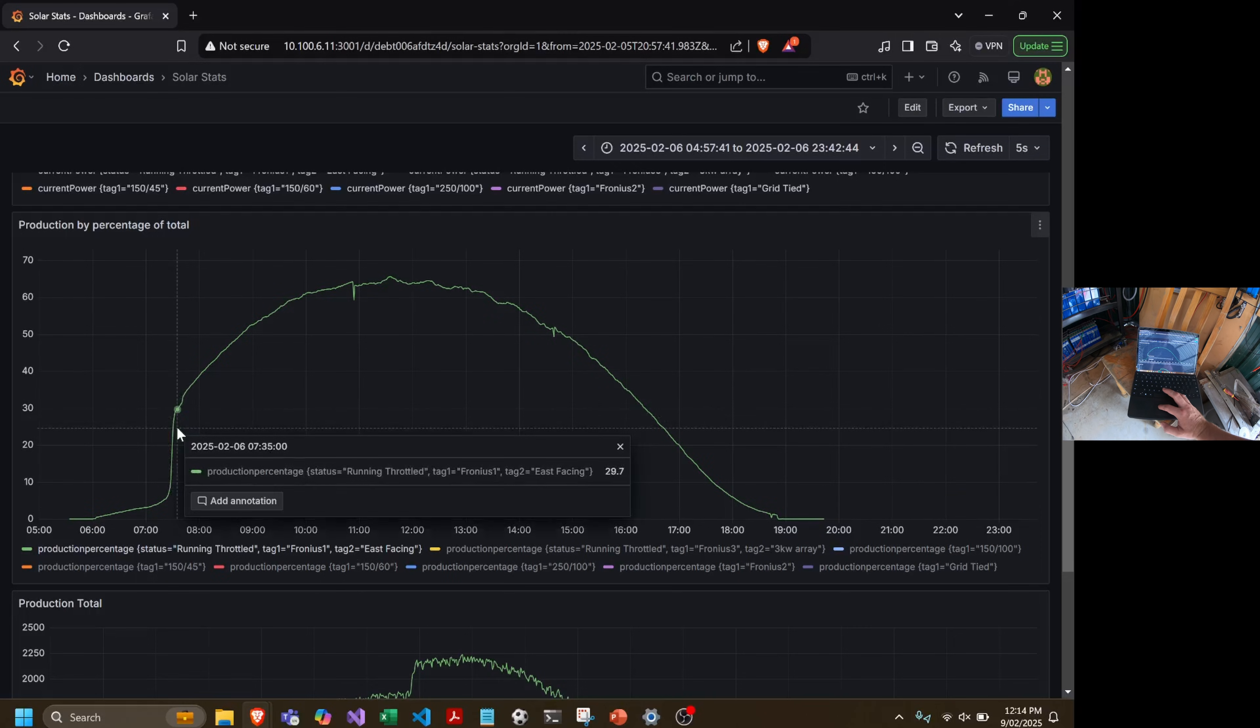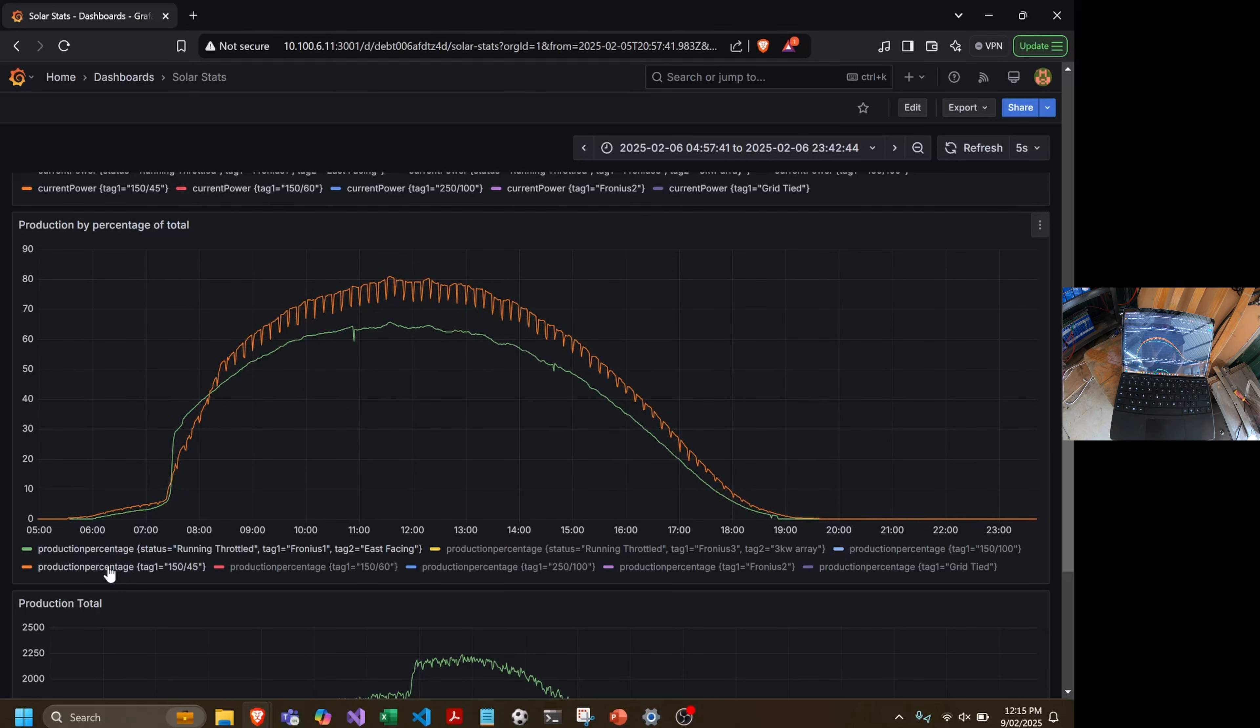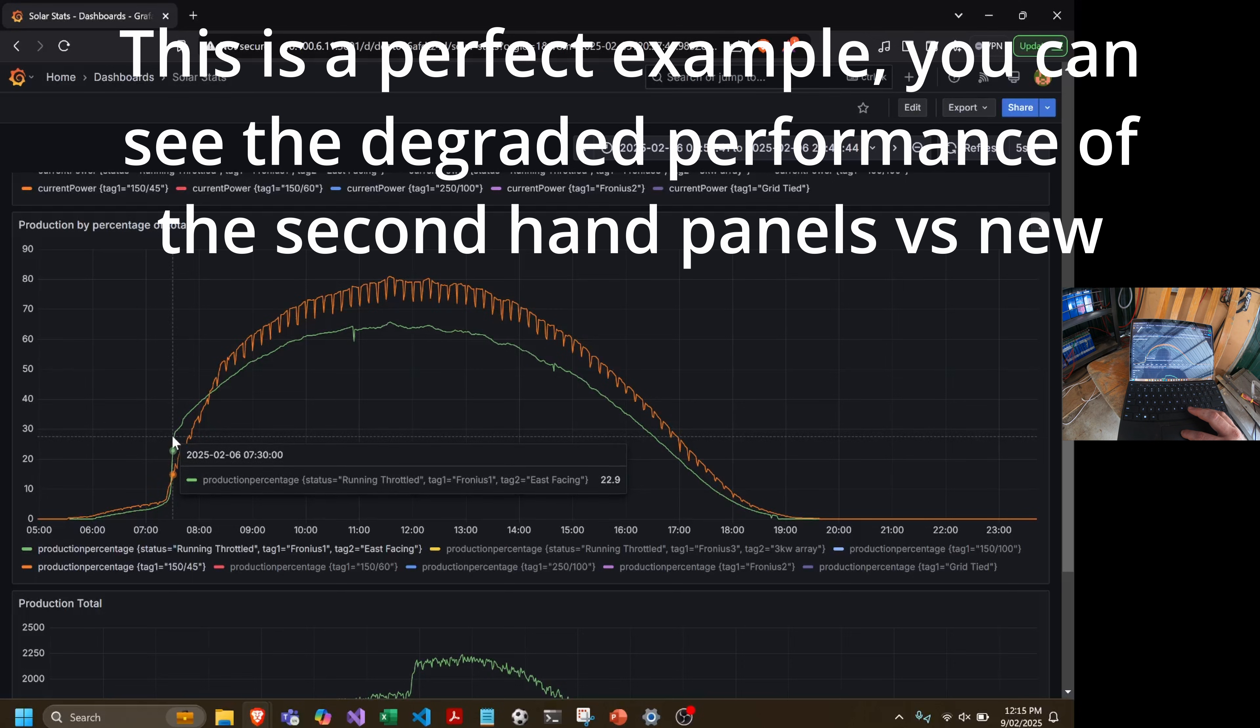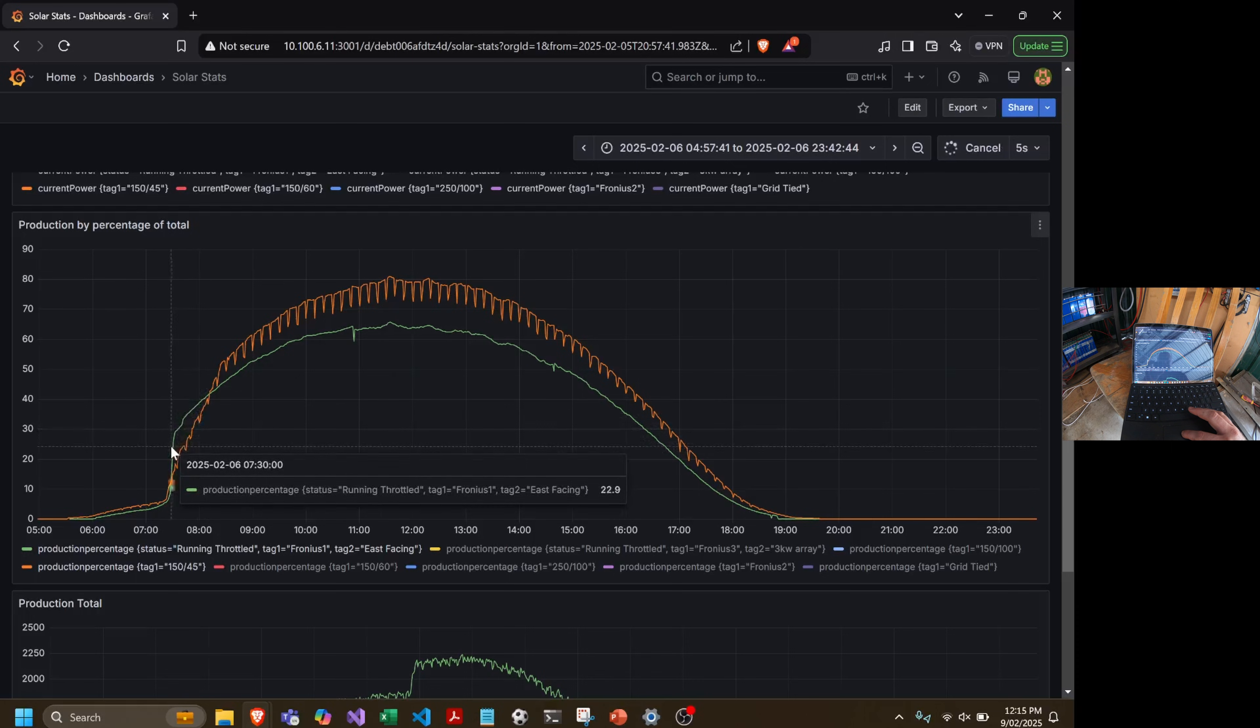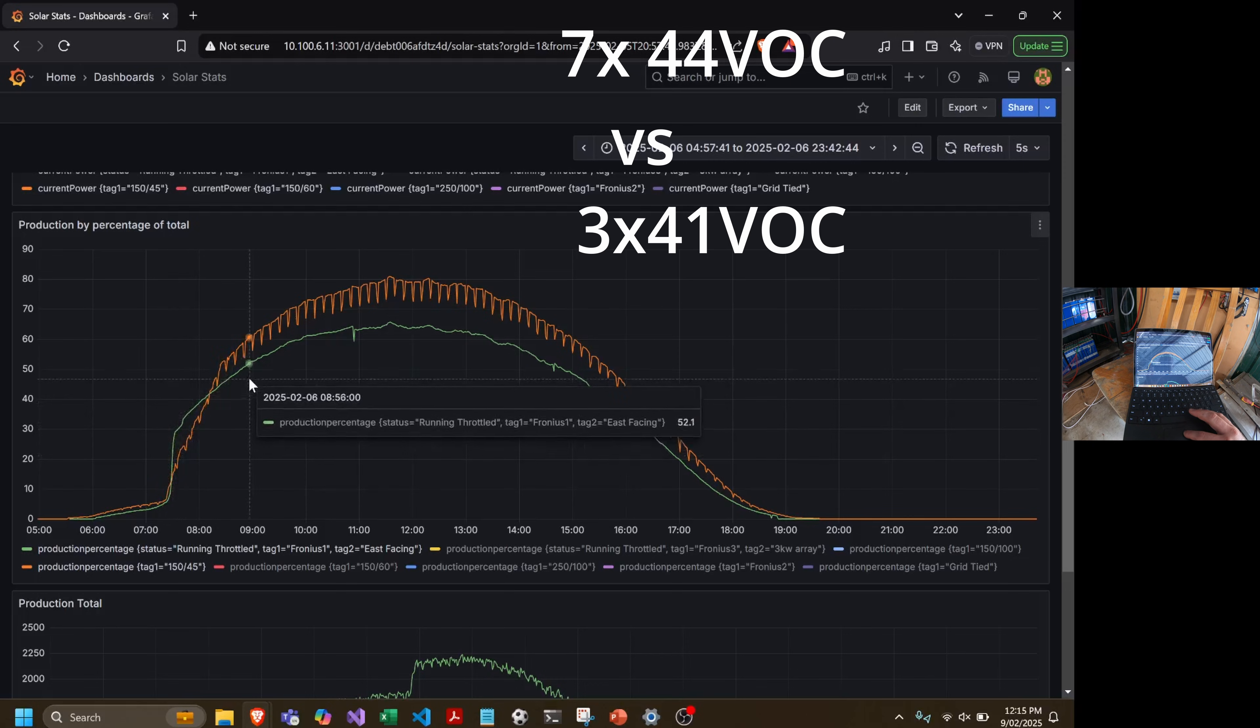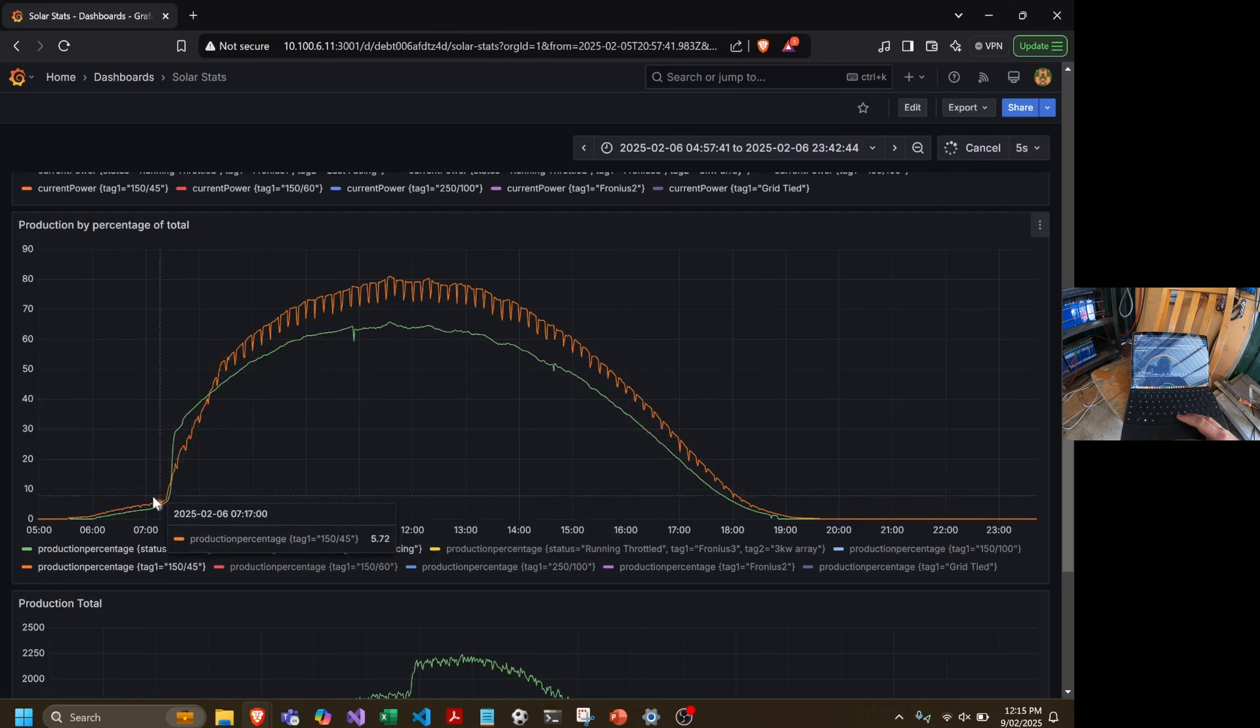That east facing roof, if we compared this one with the 150/45. The second-hand panels are actually coming on earlier, and I think this is that example where the inverter is actually running at a significantly higher voltage because we've got seven panels east facing. So they come on aggressively earlier in the morning than the ones attached to the DC MPPT.